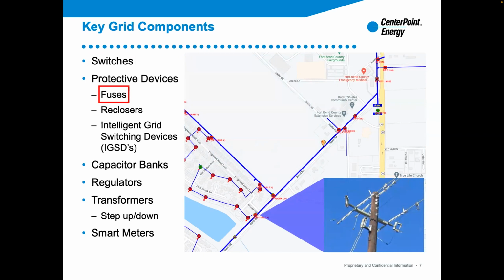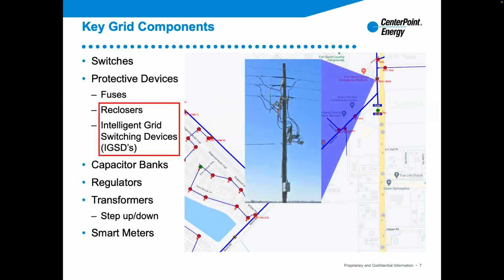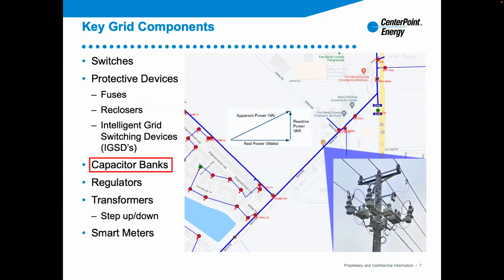We also have fuses to protect and isolate against faults on the grid. Reclosers are automated, intelligent devices that can automatically close, isolate, reclose, and transfer load between circuits across large distances. Capacitor banks help maintain power quality and unity power factor for the circuit, reducing loading on the circuit more towards unity.